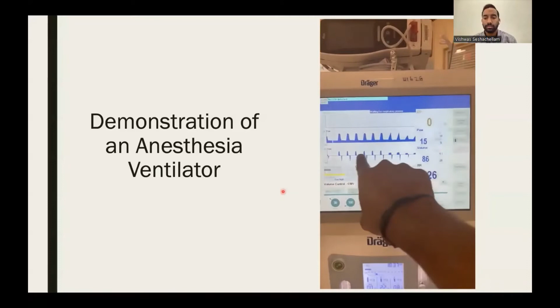So if I go to volume control, I set my tidal volume here. Peak inspiratory pressure is here. So now I'm setting the tidal volume. And you'll notice the volume here, you'll notice the waveform change. Waveform here looks very different from our pressure control waveform. That's an inspiration, expiration, inspiration, expiration.